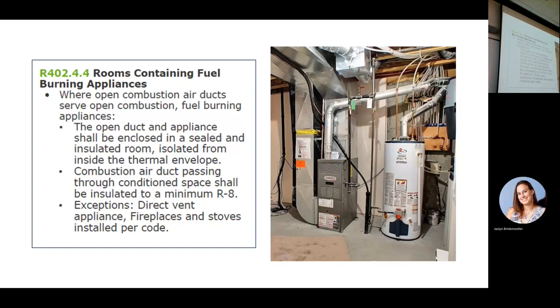It relies on stack action, it relies on chimney action to draw the products of combustion up out of the house. And since we're drawing air out of the inside of the house, as I mentioned earlier, and you can't see it, but there's a combustion air duct up behind here, we have to bring in some outside air to replace or supply what air is required for the combustion process and what gets drafted out as secondary air on your combustion.